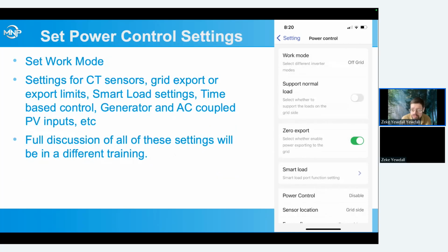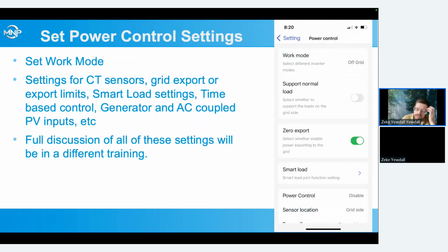Power control settings is where you set your work mode, whether we're doing off grid or self consumption, whether we're supporting normal loads, how our CT sensors are working, whether we're doing zero export. We also have our settings for time of use metering and our smart loads under power control. That's where most of our settings are, but not all of them.